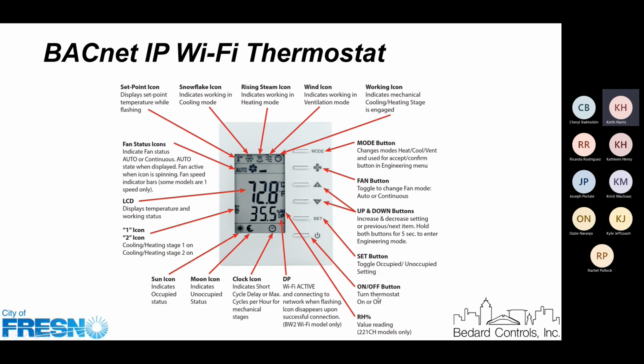We've also just recently opened up, you can actually just turn off the unit. We don't necessarily recommend that, but some people feel more comfortable just having the unit not running. The other one down here, we're not measuring humidity, so you won't see anything there. The DP disappears as soon as we actively connect it. The moon and the sun icons indicate that it's in an unoccupied or occupied mode. So you should see those depending on what the schedule is for that particular time of day for that space.